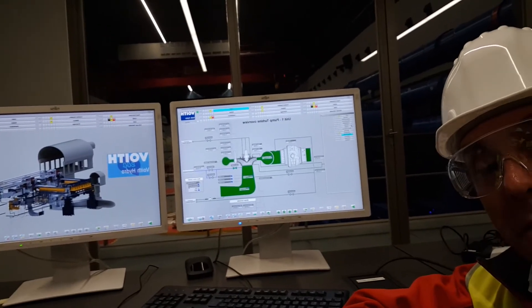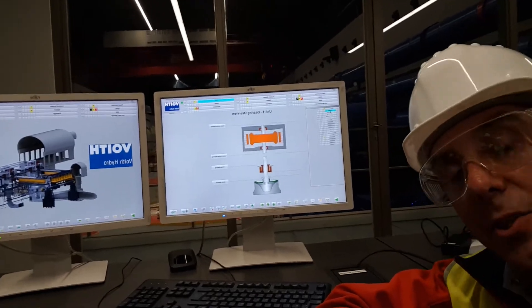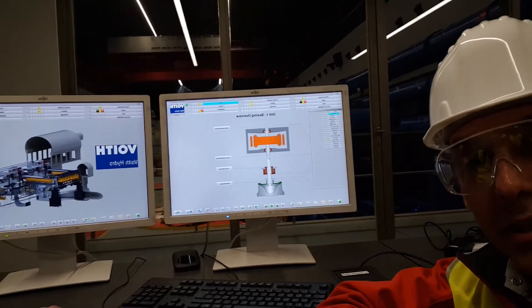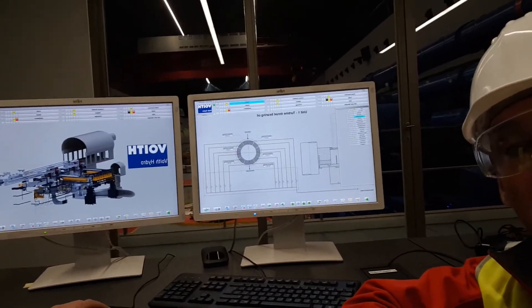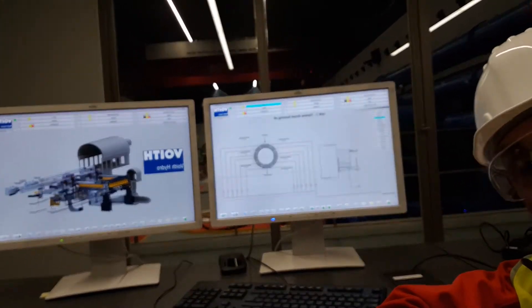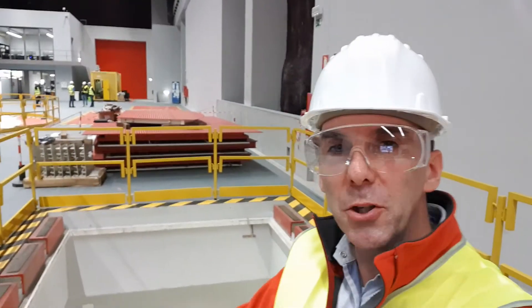For the whole plant we've seen so far, this is the distributed control system — it's part of the Voith HICON software suite. What you're seeing on the screens here is how they monitor the entire plant: all of the waterways, all of the various turbines, pumps, everything. If there are any alarms triggered by any of the sensors, this is where they pop up, and they're also sent off to the control office. The entire system is automated and monitored — this is industrial IoT in action.